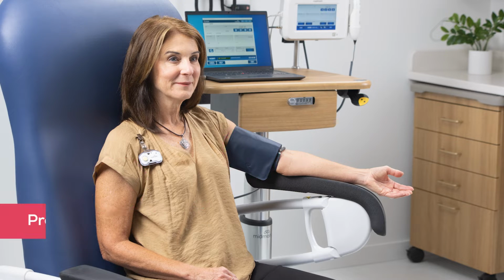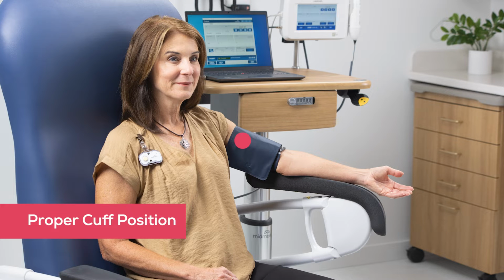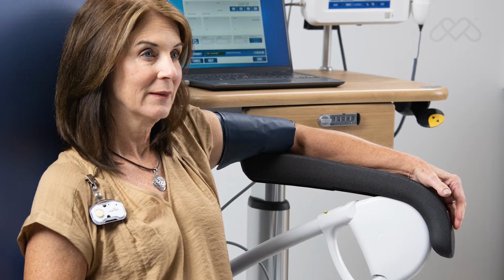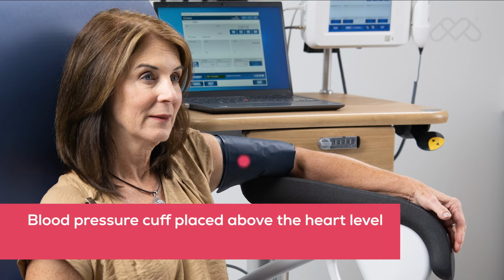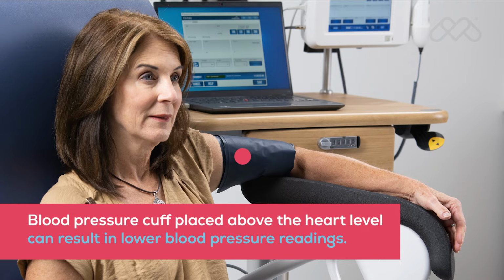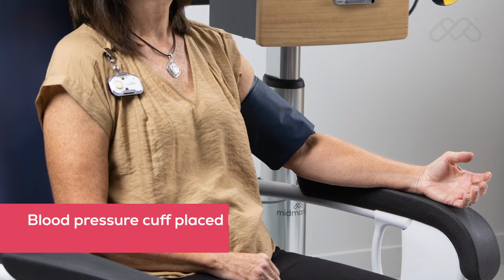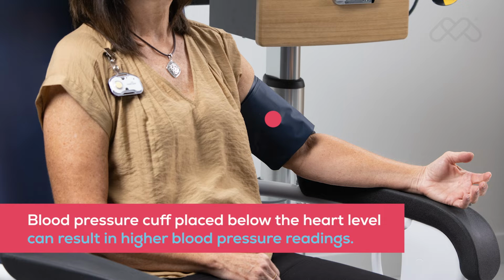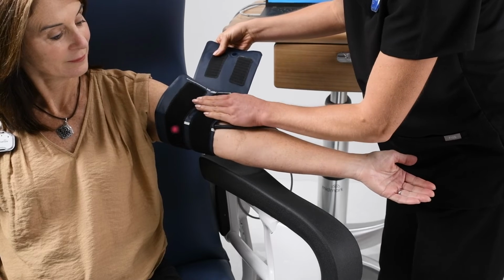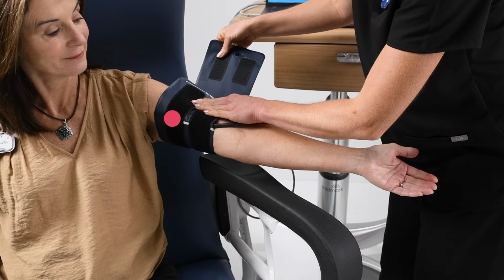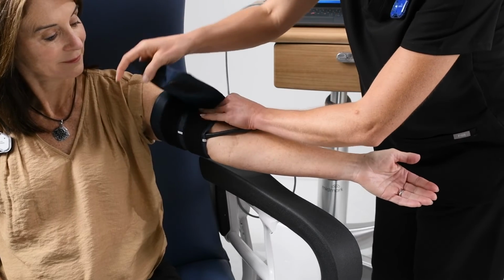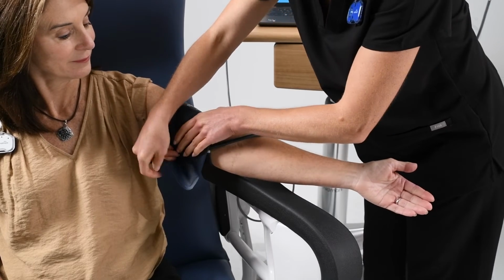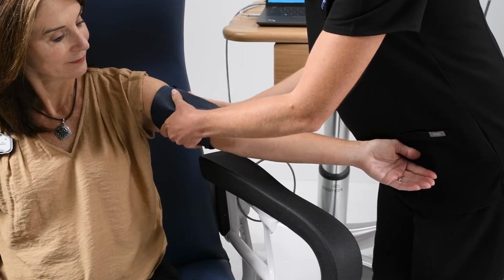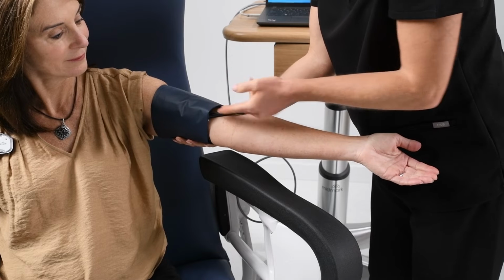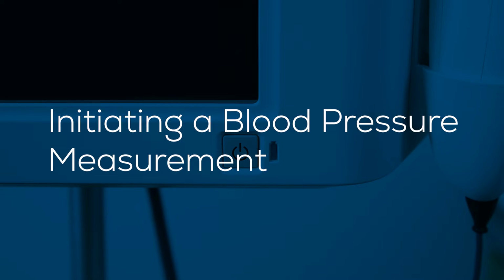The cuff should be positioned level with the patient's heart. Measurements taken with a cuff placed above heart level can result in lower blood pressure readings. Measurements taken with a cuff placed below heart level can result in higher blood pressure readings. Place the cuff brachial artery marker over or close to the brachial artery when the cuff is applied to the upper arm. For best results, wrap the cuff snugly so that there is room for no more than 2 fingers under the cuff.